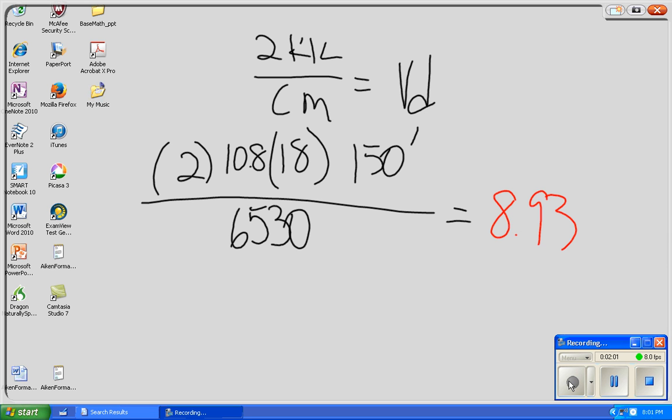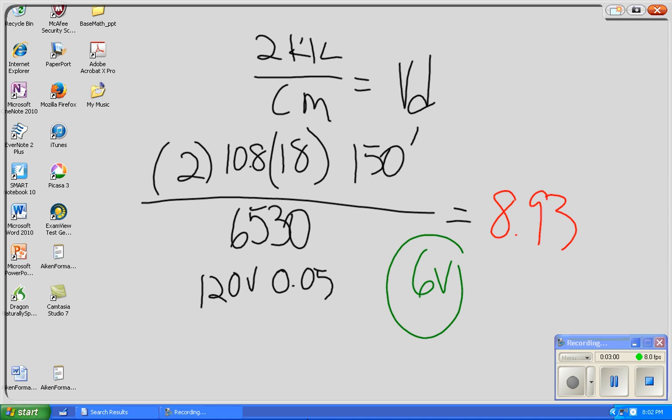Now, the code book says in a fine print note, now called an advisory, that you may have a total of 5% voltage drop from a main service. So if you have 5% and you're connected to 120 volts, you multiply it times 0.05. I had it right the first time, sorry. 5% is 0.05. So 120 times 0.05 is what? 6 volts. So even coming from a main service, that's too much voltage drop.